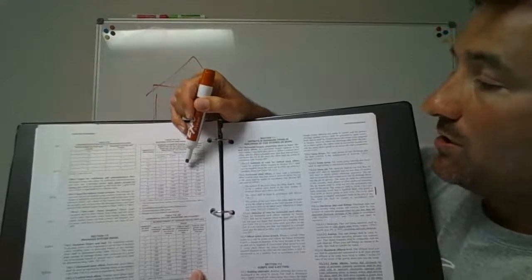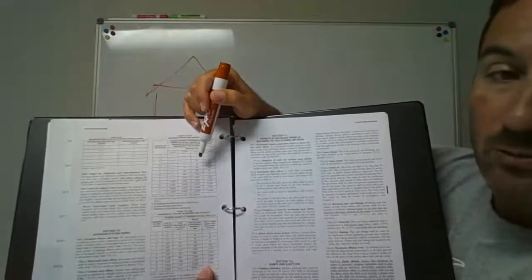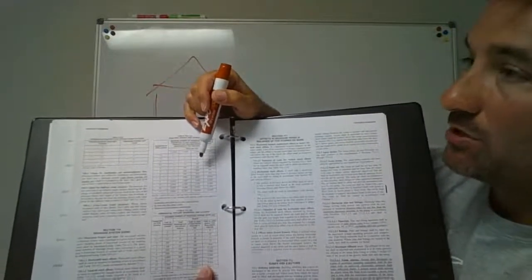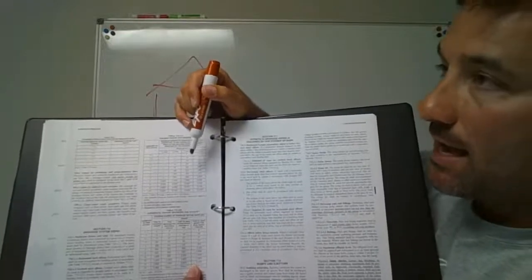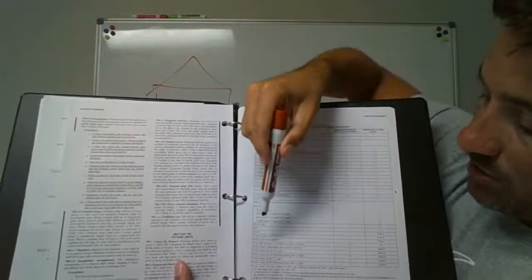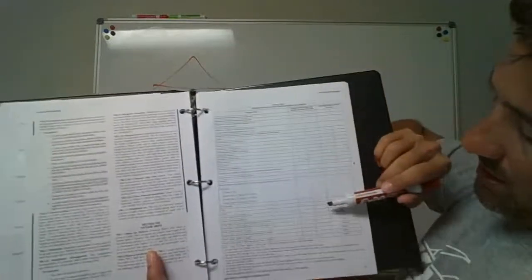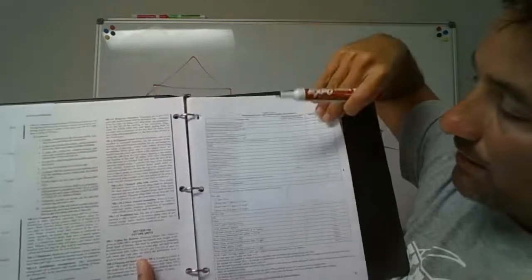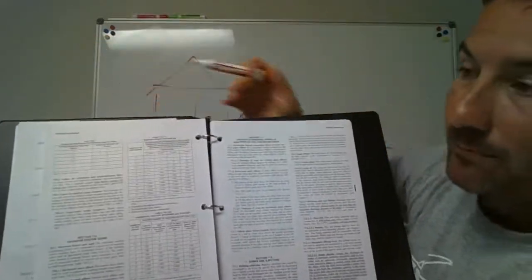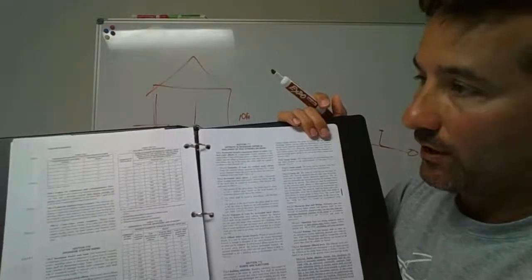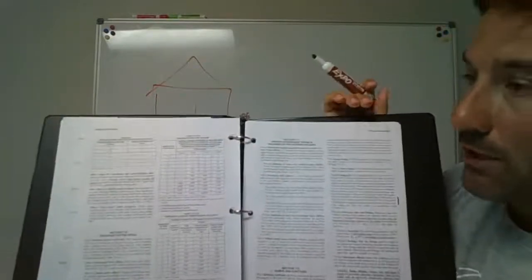Well, how about you just say, well, man, if I've got my little shop back there, I don't want to have to run all the way out of the house to go to the bathroom. So let me just throw a toilet in there. So that's going to add in, if you look back over at this page, I'm adding that water closet. In a residential 1.6-gallon flush water closet, you come down and you say, oh, that's three DFUs. So I'm going to put a half bath, and then I'm going to add one wash sink. So I've got three DFUs.